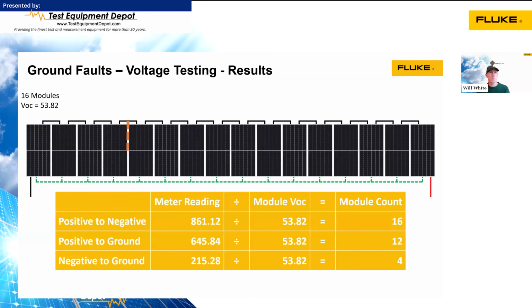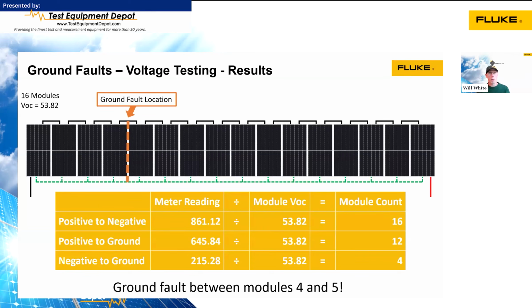So what this tells me is that there are 12 modules between the positive and the ground fault and 4 modules between the negative end and the ground fault. And that means that the ground fault is somewhere between module 4 and 5 from the negative end of this string. So what I'll do with this information now, after I've done these calculations, is go out into the field, figure out where this string is, count 4 modules in from the negative end, and that's where my ground fault should be. And I might have to do some work to figure out exactly where the ground fault is, but at least I know where in the string approximately it's located.